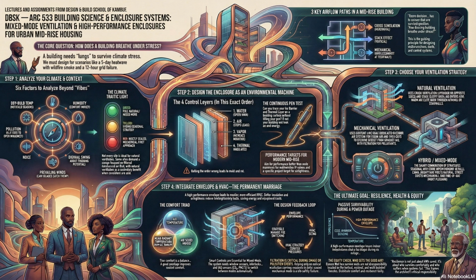Let's detail those three operational modes now, defined by that control logic. Okay, mode 1 is natural. Sensor data confirms low CO2 inside, low pollution outside, and mild temperatures. Windows are permitted to open. The DOAS is running at a minimum, or maybe it's off entirely. The building is breathing naturally, with the blue and red arrows. Okay, then mode 2, mechanical. Outdoor conditions are too hot, too cold, or too humid. Windows are instructed to remain closed, the interlocks are engaged, and the full DOAS system, coupled with the HRVs or ERVs, runs at the required ventilation rate, providing high-quality conditioned air.